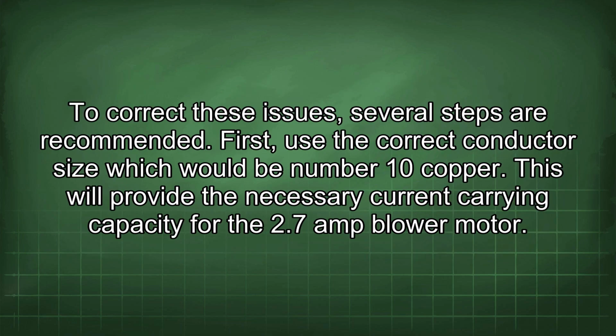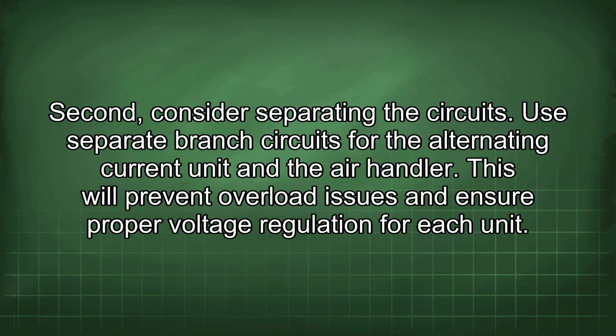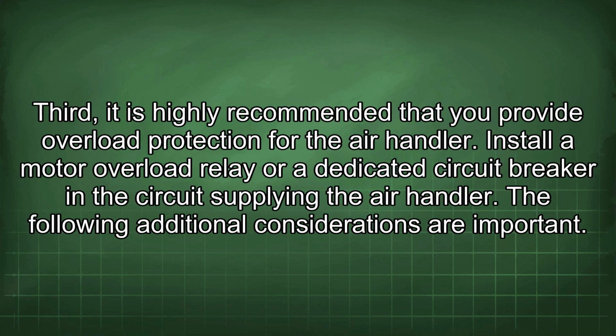To correct these issues, several steps are recommended. First, use the correct conductor size, which would be number 10 copper. This will provide the necessary current carrying capacity for the 2.7 amp blower motor. Second, consider separating the circuits. Use separate branch circuits for the alternating current unit and the air handler. This will prevent overload issues and ensure proper voltage regulation for each unit. Third, it is highly recommended that you provide overload protection for the air handler. Install a motor overload relay or a dedicated circuit breaker in the circuit supplying the air handler.